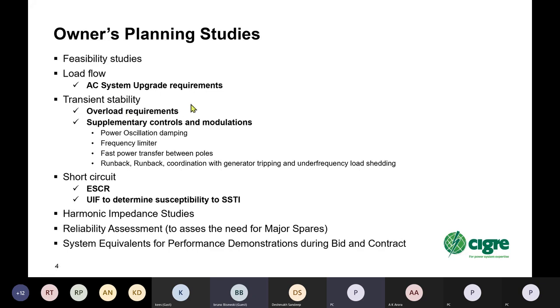objective is to determine overload requirements, and to define, if necessary, supplementary controls and modulations, which could include power oscillation damping, frequency limiter, fast power transfer between poles, run back, run up, coordination with generator tripping, and under frequency load shedding.